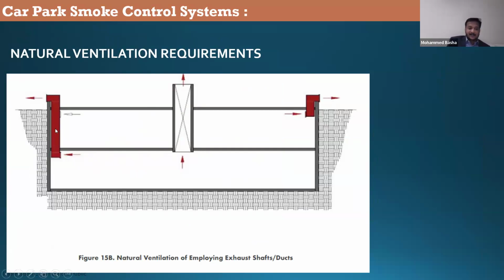So you can have a duct without a fan. It can take the smoke out. You have a duct without a fan at separate levels, and a normal shaft to take the smoke out. This is more than sufficient for QCDD. But if they ask you to provide a CFD analysis, you have to prove it. So the main concept of why they allow the natural ventilation system is the car park being less than 2000 square meter. You may have a question: why do I need an engineered smoke control system if it is more than 2000 square meter?